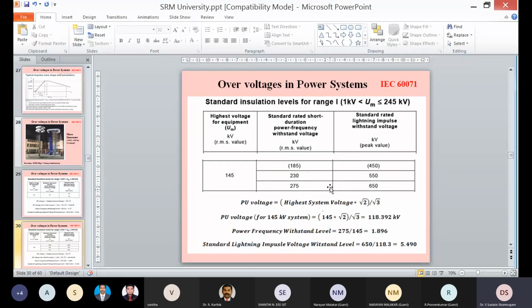You can see here also three values are given. If your grounding system is very proper, you can take 185 and 450. If not, you have to go for the highest. Most of the time we are going for the highest value only. So what they have told us, for a 145 kV system, the lightning impulse voltage is 650 kV. So again per unit I have calculated. Per unit is nothing but higher system voltage into root 2 divided by root 3.